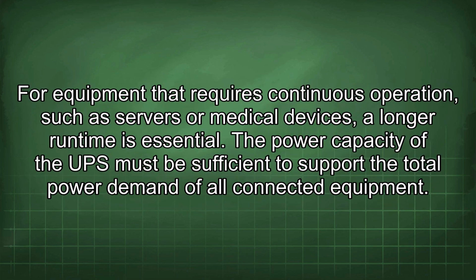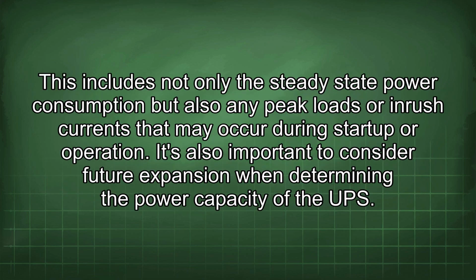For equipment that requires continuous operation, such as servers or medical devices, a longer runtime is essential. The power capacity of the UPS must be sufficient to support the total power demand of all connected equipment. This includes not only the steady-state power consumption, but also any peak loads or inrush currents that may occur during startup or operation. It's also important to consider future expansion when determining the power capacity of the UPS.